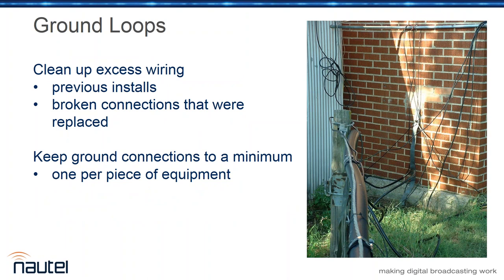Anywhere you have a parallel path, or a connection that got broken and rather than splicing it you ran a new wire, the old stuff should be pulled totally out. Especially remember that ground connections are frequently uninsulated copper, so one strap laying on top of another is partly a parallel path and partly a capacitor—all kinds of issues. So by all means, keep things as tidy as you can. Do the housekeeping to remove the old stuff when you're putting in the new.